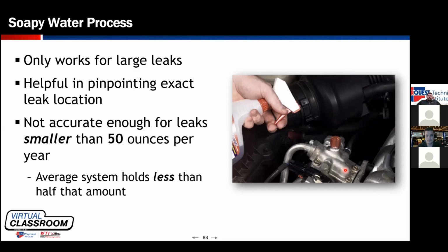If you're working in an area where your leak detector is going crazy, you've got contamination, it's hard to pinpoint where that leak is. Soap bubbles can be helpful to start to pinpoint where that leak is. My personal preference for soap solution to find leaks, I like white wall cleaner. It's what I find works the best for me.